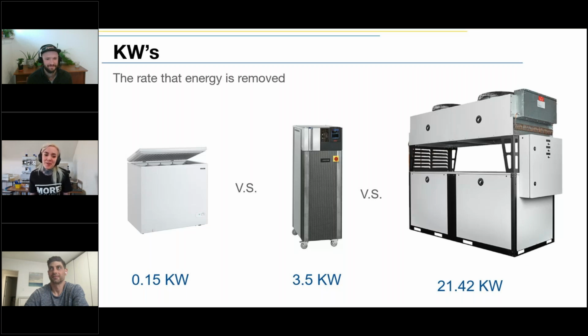So look at the volume of fluid you really need to chill. That way, every time you buy a new piece of equipment, calculate that jacket volume, calculate the distance it has to travel. I can't tell you how many people build their C1D1 in the middle of the building, making them very poor candidates for an outdoor chiller, because now we have to plumb that chiller 85 feet to reach the C1D1. This is an infrastructure problem you can fight for years, or thoughtfully consider upfront, because you can estimate that jacket volume and the thermal demands of piping it as far as it needs to go.